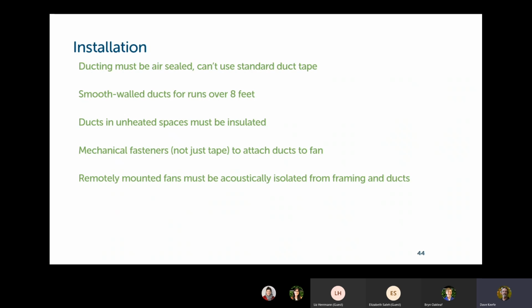Remotely mounted fans must be acoustically isolated from framing and from the ducts. You'll notice that the fans that are mounted within 4 feet of grills, as I've already said, have to meet a sound requirement. They have to be below 1.5 sones. If you mount the fan remotely, it does not have to meet any particular sound requirement, but they do require that you mount it in such a way to minimize the amount of vibration and noise that's transferred to the framing.